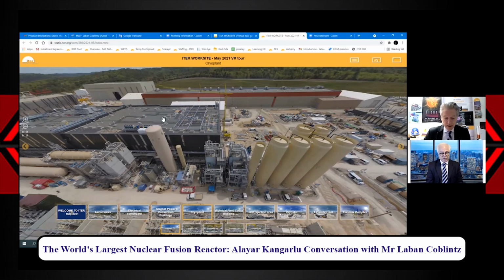So going inside, do you actually liquefy helium on site, or do you purchase liquid helium? No, we purchase the helium, but we don't manufacture it. That 25,000 metric tons, as you know, helium is a very precious resource, so we don't plan to restock. This is a leak-free facility, it has to be leak tight, but we take the incoming helium gas...